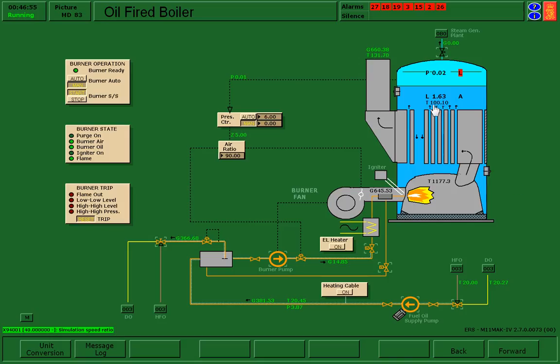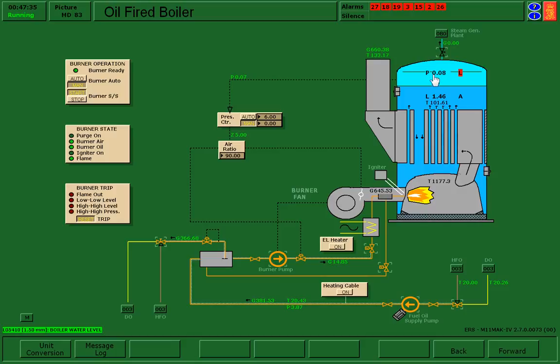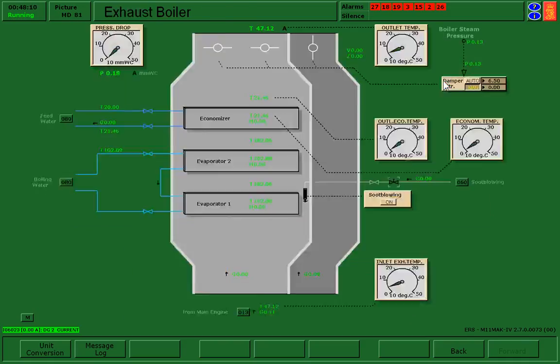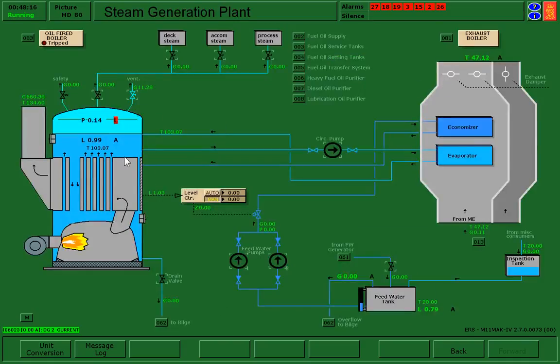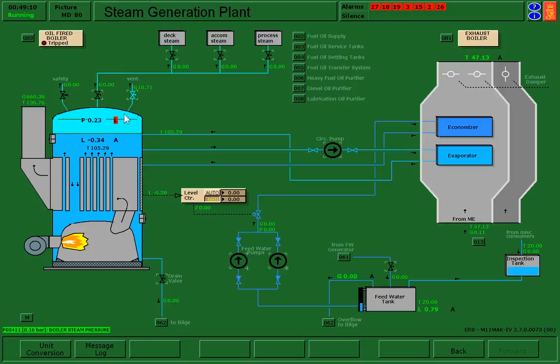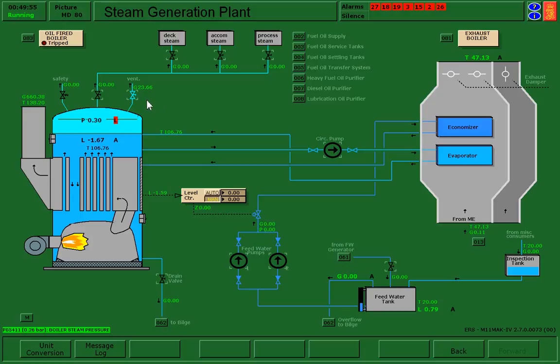We can see that we're at about 100, our typical boiling point for water exposed to the atmosphere, and we are just starting to build a little bit of pressure inside the boiler. What's happening is we are filling up this cavity with some steam. It's starting to displace the air that's inside and everything is coming out of the vent. We're starting to get some flow out of the vent, and we're going to leave this open for a little while until we're confident that we've gotten rid of a lot of the air that's inside the boiler.